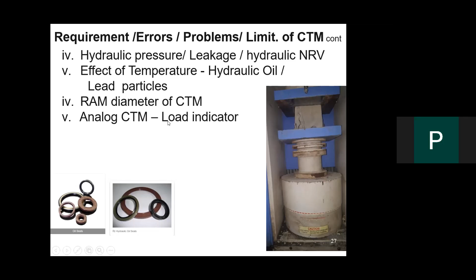Again, what I already talked about the analog system, the load indicator, I can easily change and calculate the things. Not only that, there are two indicators, one red and one black. The black one is the live one, and the red one is the stationary, or you can say false one. Another problem with the analog machine is the indicator which gives the pressure. The live black indicator going upside should not give a thrust to the dead indicator, because whenever the machine stops, the live indicator comes back down to zero, and our dead or false indicator will stop at that place.